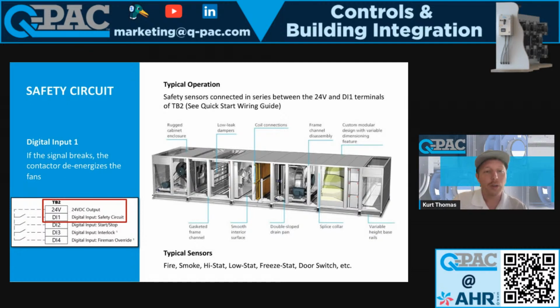Safety circuit. So typical operation, right? There are a lot of different sensors for your safety circuit, right? You don't necessarily need all of them, but the common ones are high stat, low stat, and freeze stat. So if you want to make sure that you're not blowing out any ductwork, crumpling any ductwork upstream, or if you want to make sure your fans are not operating whenever your coil has frozen over, then you can add those in series. Please add them in series and not parallel. I have seen that happen.